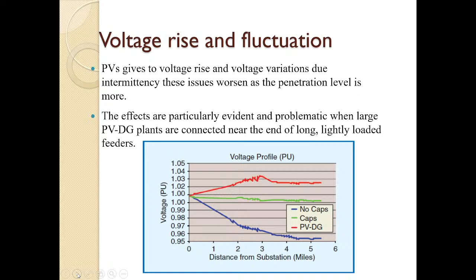However, when you go for solar photovoltaic panels, especially on rooftops, this phenomenon will be reversed, and you will get characteristics that are red in nature based on where you put the solar photovoltaic panels. The feeder end point, which had a reduced voltage, will now go to an increased voltage in the process, and the culprit is solar photovoltaic penetration into the system.